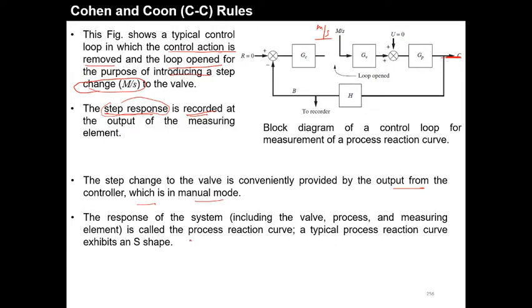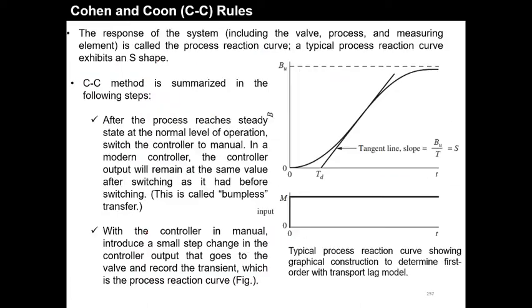Whatever the dynamic response of the system comes, it is recorded and that curve is known as the process reaction curve. This curve is similar to the general open loop curve — the typical process reaction curve exhibits an S-shape. We then find the inflection point, where the nature of the curve changes from convexity to concavity or vice versa. At that point, we draw the tangent.